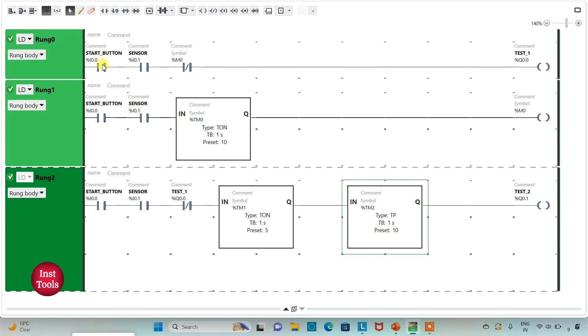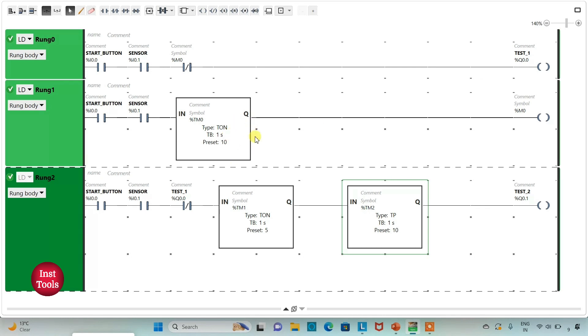When the start button is turned on and the sensor gets activated — detecting the presence of an object at the bench — Test1 will start. There will also be a delay of 10 seconds for M0 to become true. When M0 gets true after 10 seconds, the current will not flow through the normally closed contact and Test1 will end after 10 seconds.